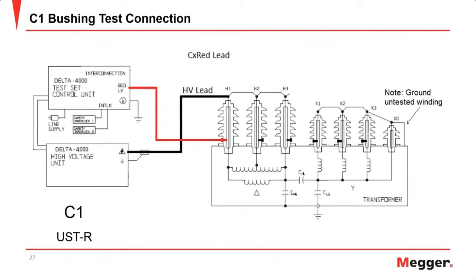If you have multiple bushing taps uncovered and they are just left open and not grounded, when you energize at 10 kV, that bushing tap will also see that 10 kV, and it could cause irreparable damage to that bushing. So please, when you are doing your C1 tests, only have one of the bushing taps uncovered and make sure that it is connected to the measurement lead before you start testing.